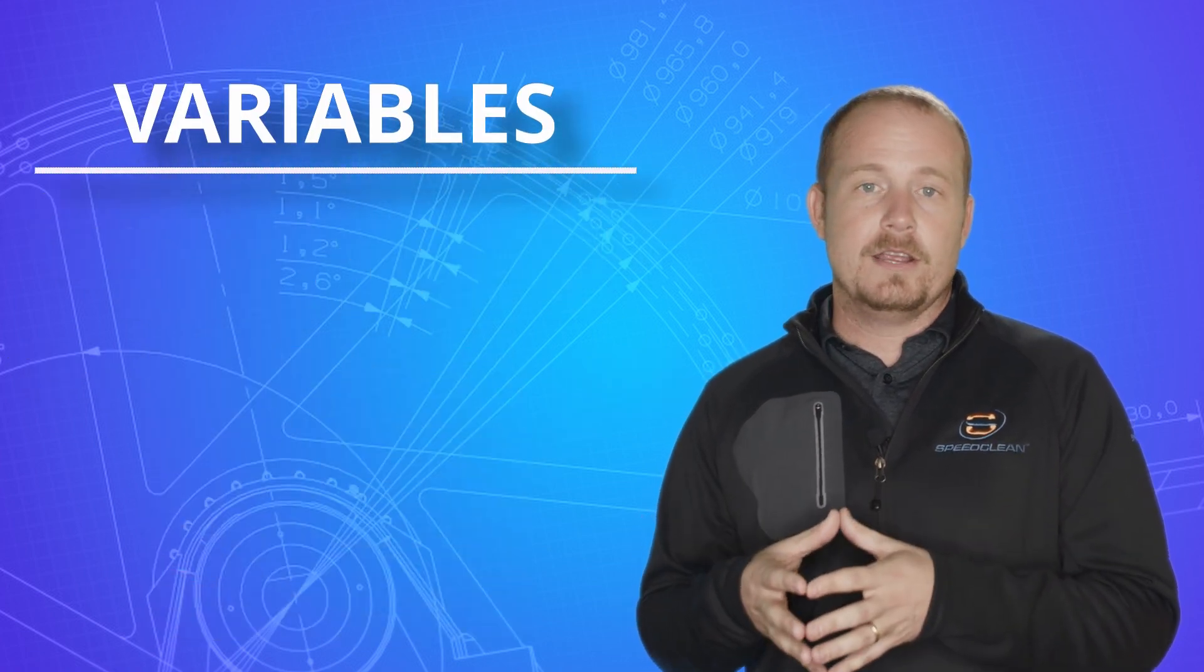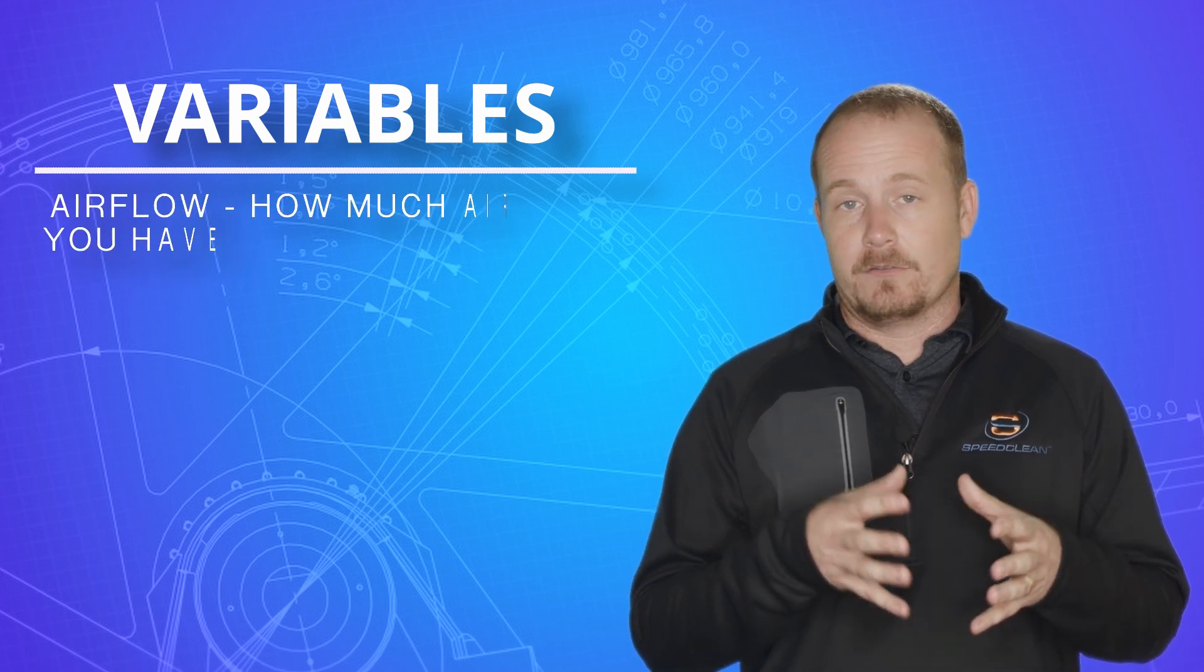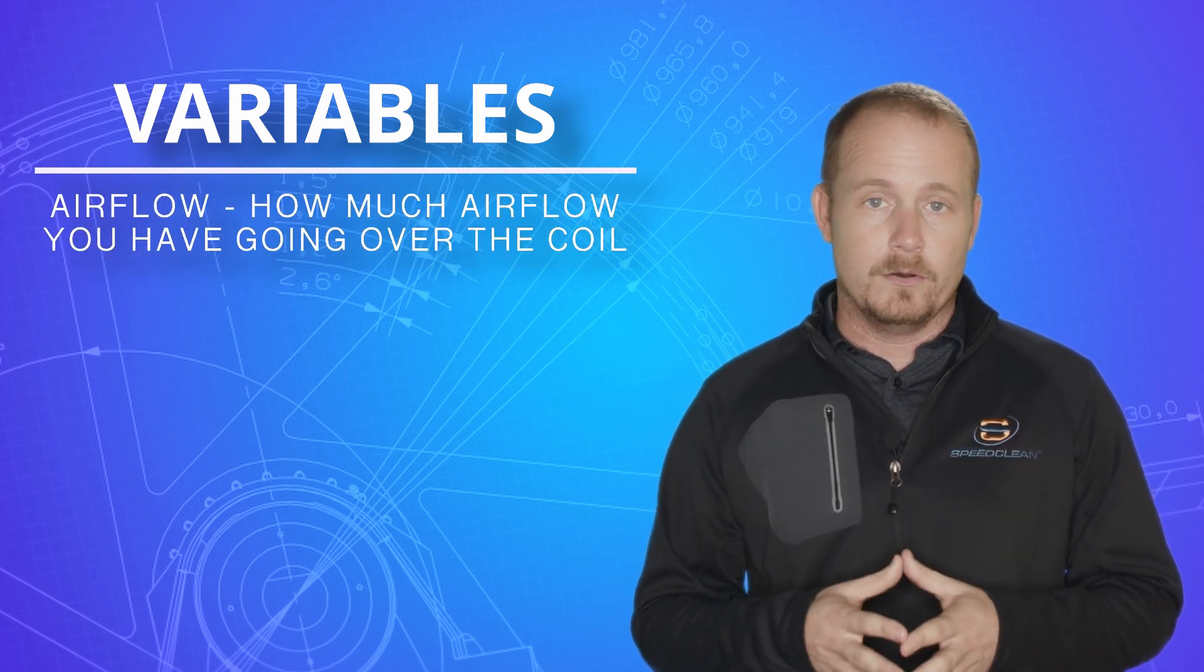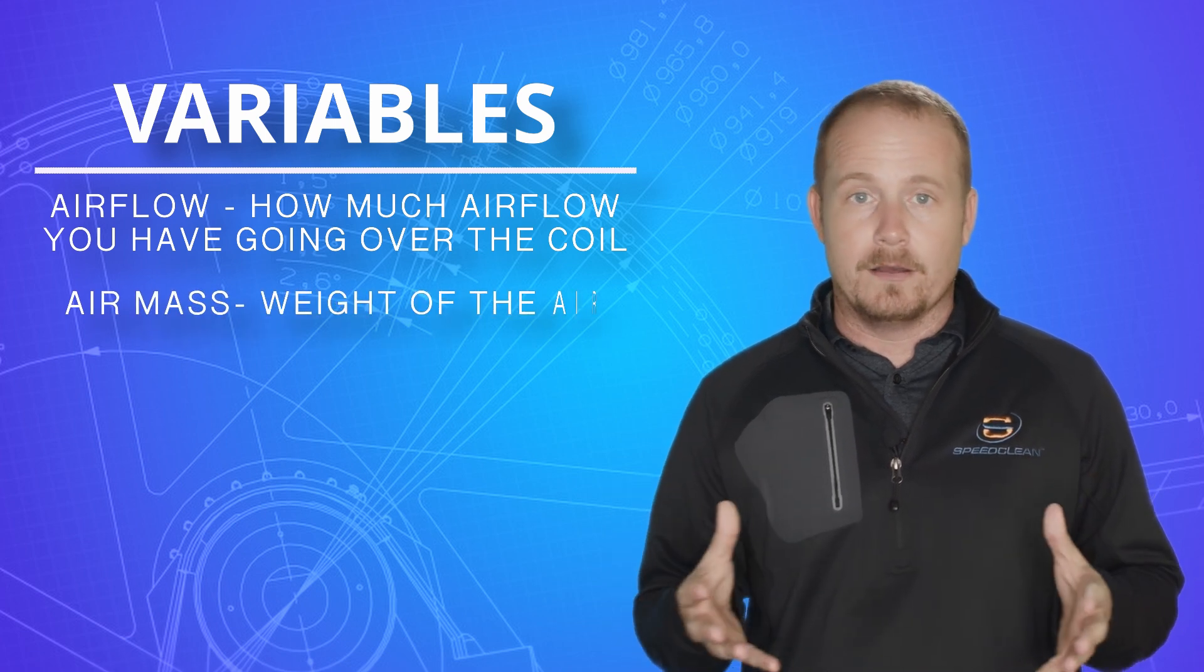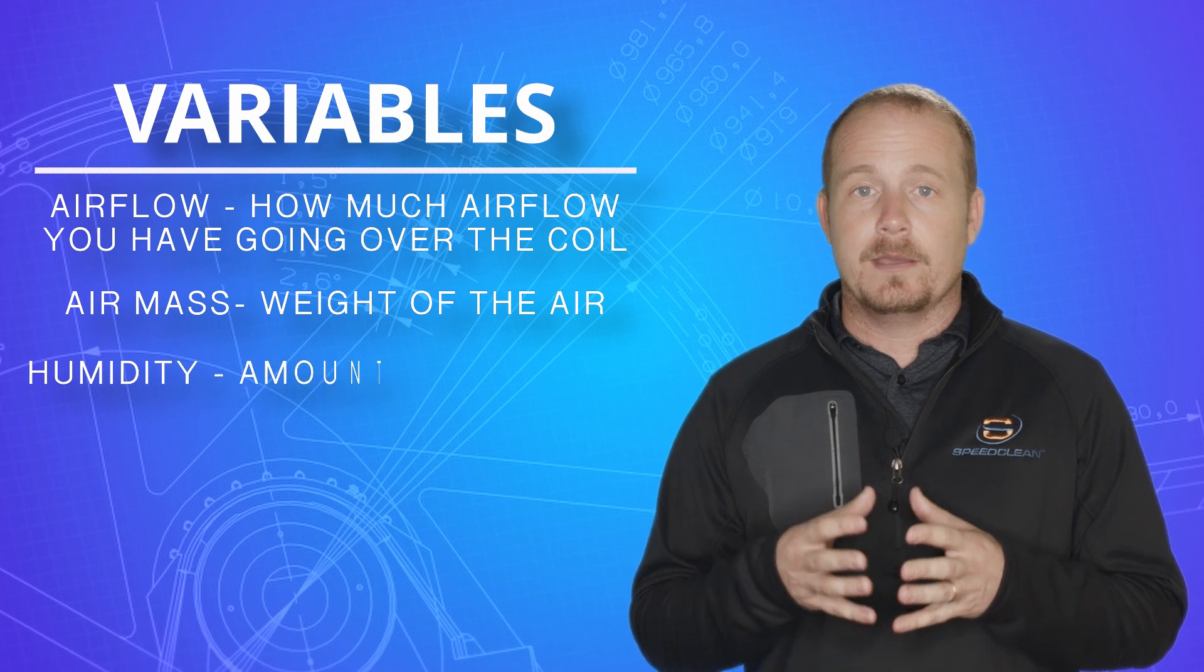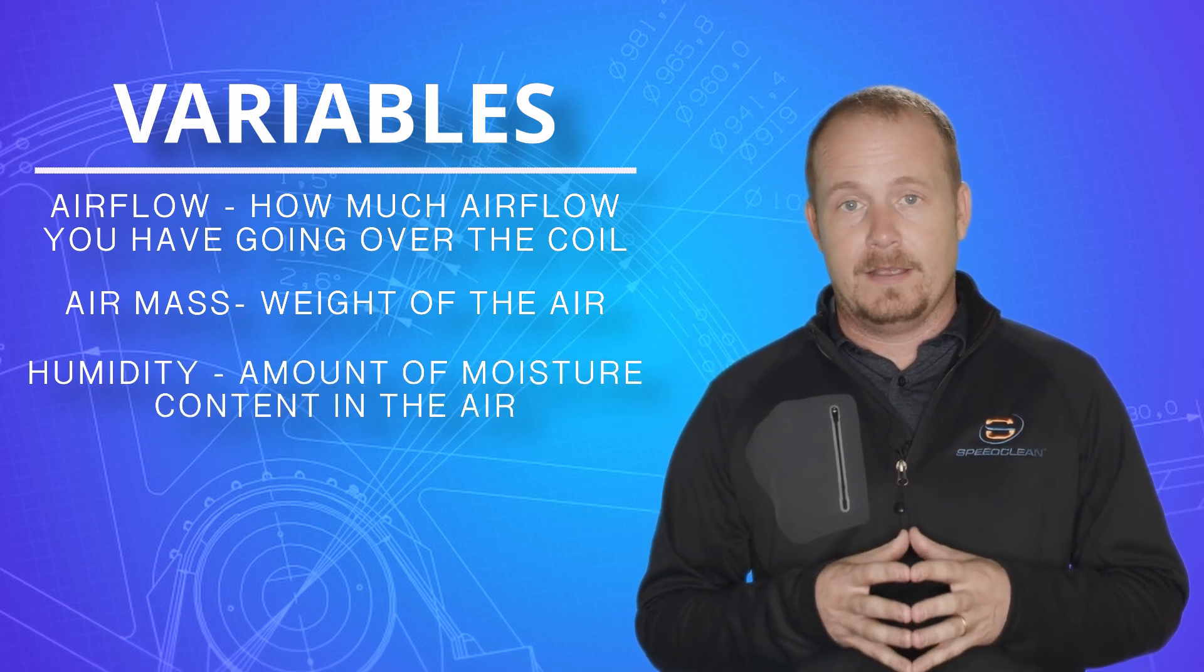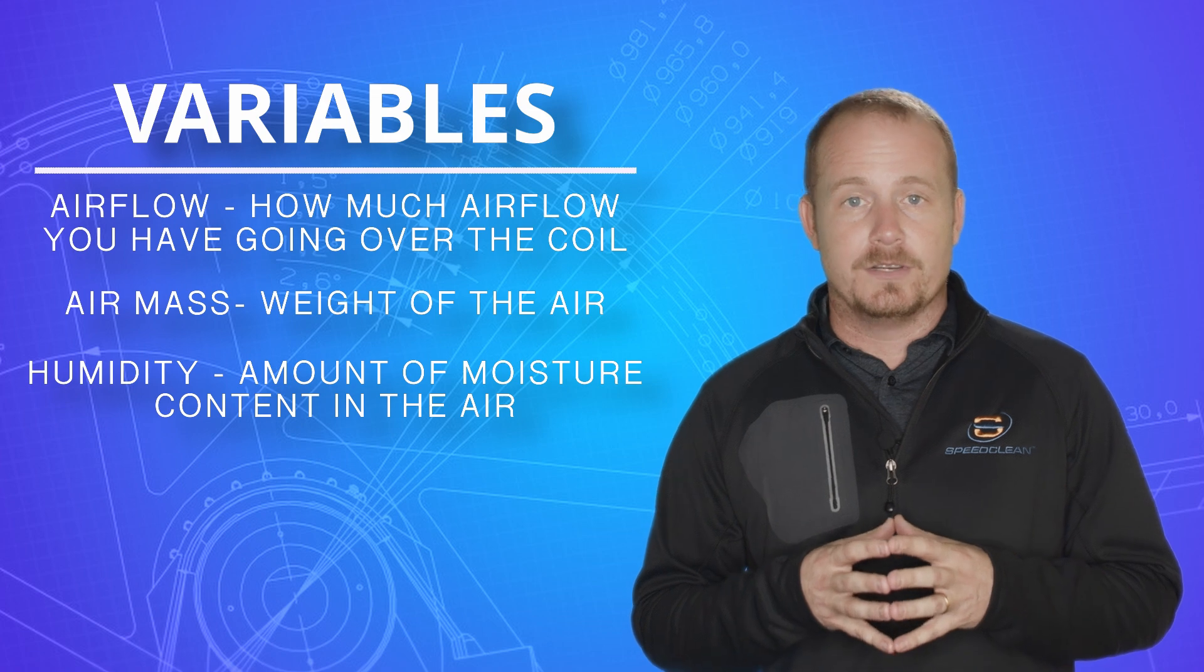You get a lot of variation in delta T based on airflow, how much airflow you have going over the coil, air mass, so what is the weight of the air, which does change. And then also the amount of humidity or moisture content in the air also changes what your delta T target is going to be.